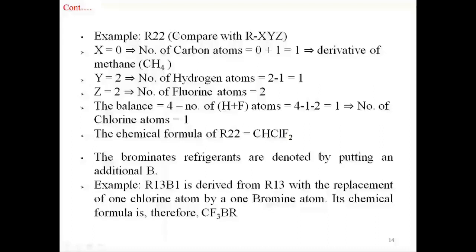Example: R22. Here we have only two digits, so comparing with Rxyz, x = 0, meaning number of carbon atoms = 0+1 = 1, i.e., it is a derivative of methane. Y = 2, so number of hydrogen atoms = y−1 = 1. Z = 2, so number of fluorine atoms = 2. The balance (chlorine atoms) = 4 − 1 − 2 = 1. The chemical formula of R22 is CHClF₂. It is also known as HCFC-22 (hydrochlorofluorocarbon) because it contains carbon, hydrogen, chlorine, and fluorine.